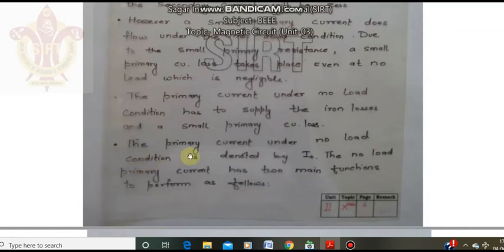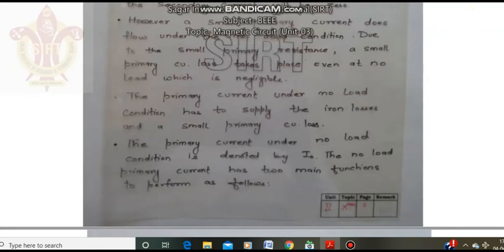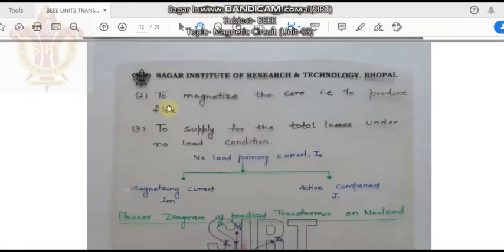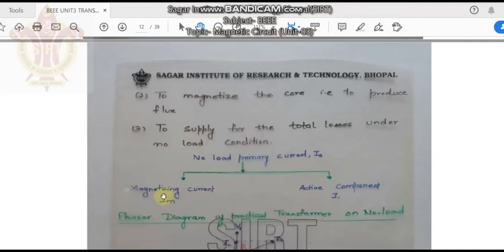The primary current under no load condition is denoted by I naught, and this no load primary current has two main functions: first, to magnetize the core, that is, to produce flux, and second, to supply for the total losses under no load condition. So the no load primary current I naught can be divided into two components: the magnetizing current component, denoted by Im, and the active component, denoted by Iw.